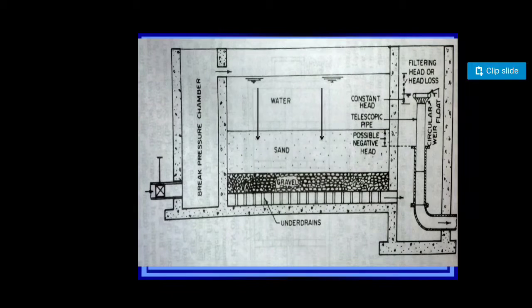Whatever we have with the filter media, there is an amount of suspended solids that was coming with the influent, which is now entrapped over the surface of the filter media, and we scrape that layer, right? So this is a physical process in which we are manually scraping a layer which has clogged the pores of the filter media.